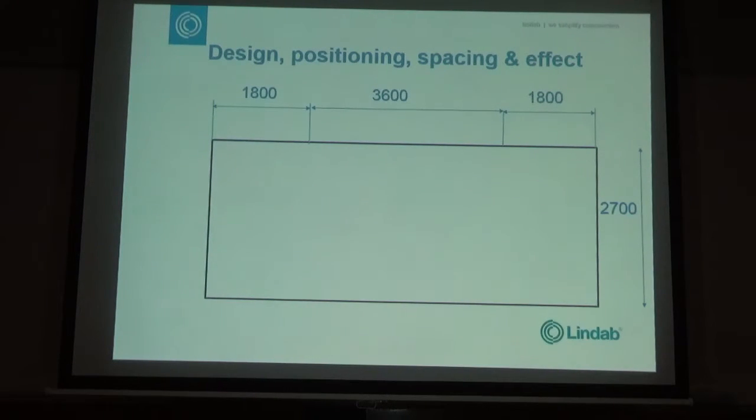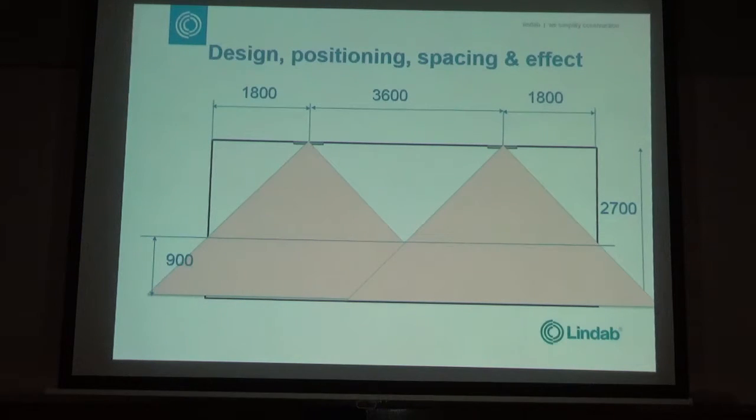What I did is a little experiment. I did a couple of quick calculations, and this is a cross section of a 56 square metre classroom. If we put two panels in the classroom, that's the sort of spacing you'd have for them. That's your effect of radiant heat, and that's your deemed occupied zone, 900 millimetres. So when your class is sitting there and it's only warmer to 900 millimetres, it means that all that part is colder than that part of the wall. So the people sitting against this wall are going to be cold, because you're going to lose temperature really quickly to that.